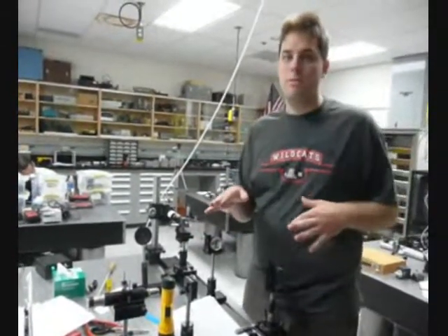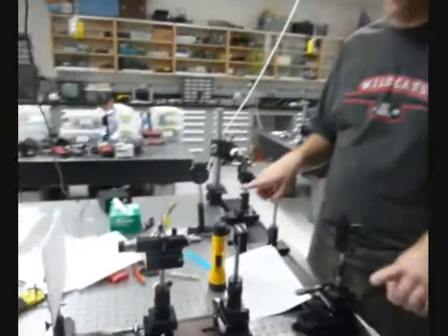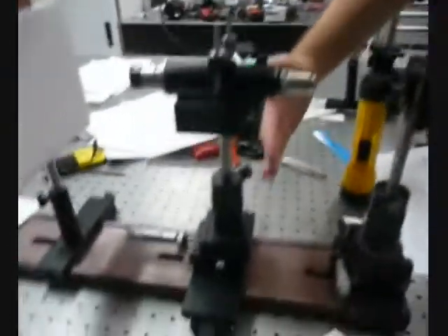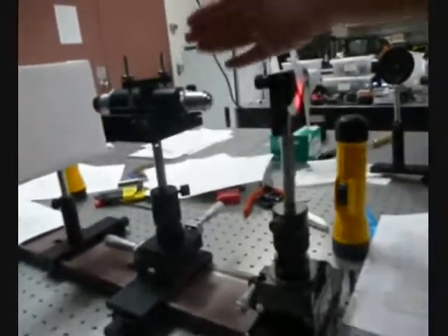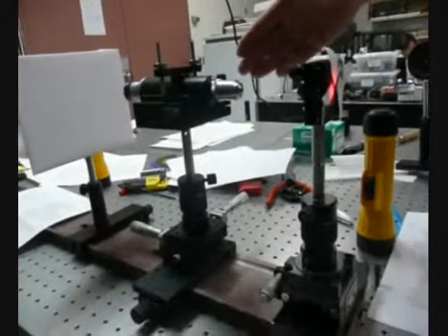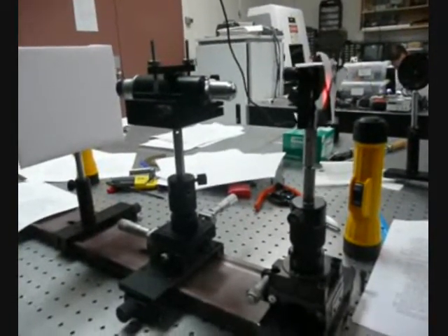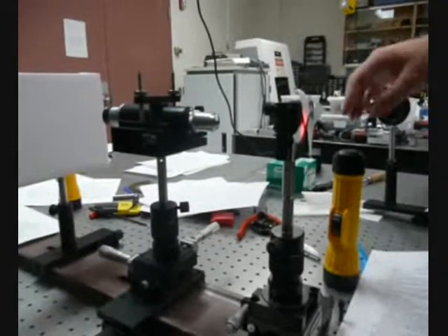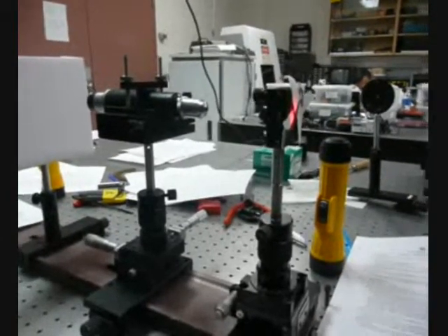To measure the tangential coma, we send the light through only one of the outside horizontal holes, and then we move the microscope along the Y direction until our beam becomes focused back over the crosshair, and then we record those positions. That distance from where the center hole is over the crosshair to where the outside holes are over the crosshair should be the same for both of the outside holes if our alignment was perfect. It was a little bit off for us.